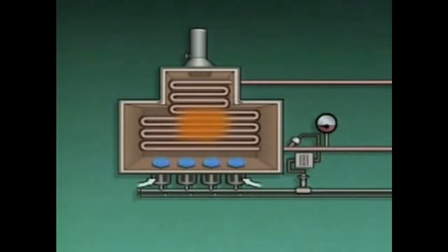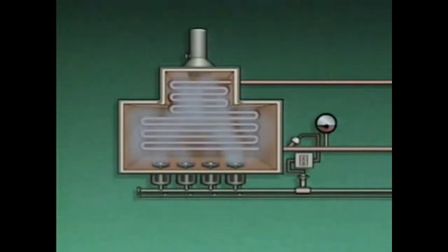If this airflow problem is not corrected, the burner flames could go out. Eventually, there may be so much fuel built up inside the furnace that if there is an ignition, it could literally blow the entire furnace apart.